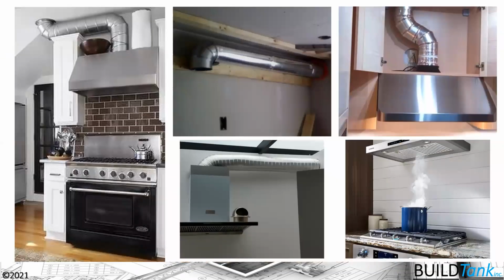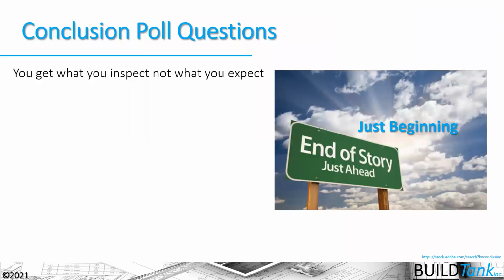And then for hoods, again, you have that exception. If you have a 6-inch duct with one elbow, like the middle pictures here, you don't have to test it, but you have to be able to confirm that that's been installed. That picture on the left here would not be compliant. You would have to then measure the flow rate there and ensure that you're getting at least 100 CFM through that system. So to conclude, ultimately you get what you inspect, not what you expect.